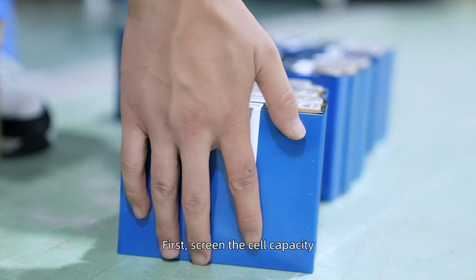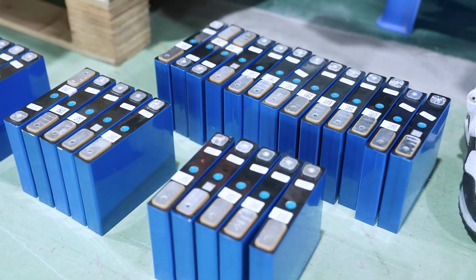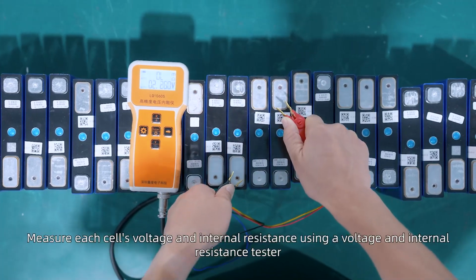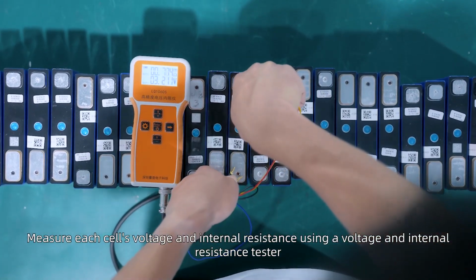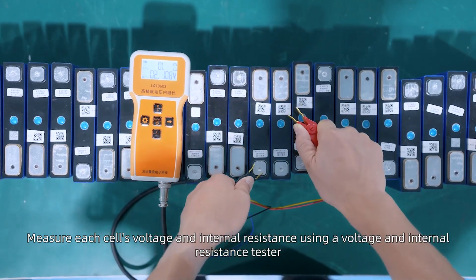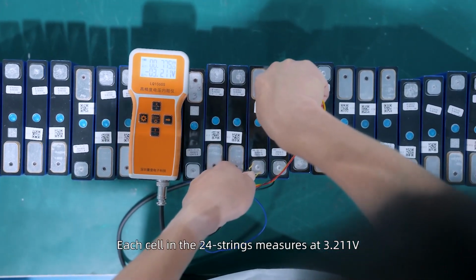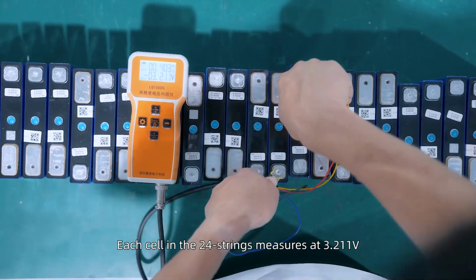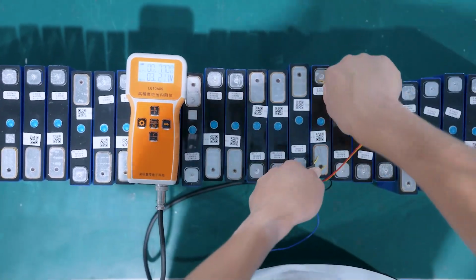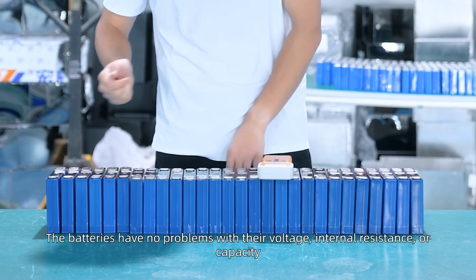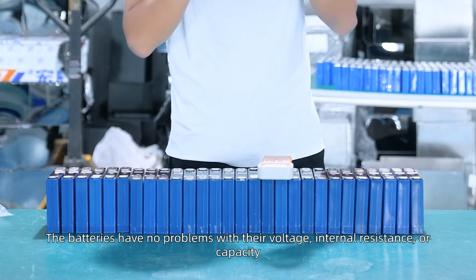First, screen the cell capacity. Measure each cell's voltage and internal resistance using the voltage and internal resistance tester. Each cell in the 24 strings measures at 3.211 volts. The batteries have no problems with their voltage, internal resistance, or capacity.